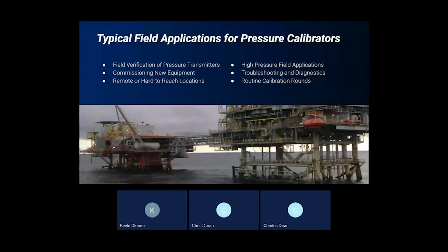Just before we move on, some field applications for this, like what is this used for, if you're wondering. They're frequently used for field verification of pressure transmitters, where technicians need to confirm accuracy on site without setting up multiple tools. It's ideal for commissioning your new equipment, especially during startups when multiple pressure points are needed. Remote, hard to reach locations where those full kits can't really get to, carrying a single integrated device makes a big difference. It's strong for troubleshooting. And then during your routine calibration rounds, which at the end of the day, that's the meat and potatoes of what this presentation is about, your calibration. This is a good tool as a reference tool to maintain faster and more consistent workflow.